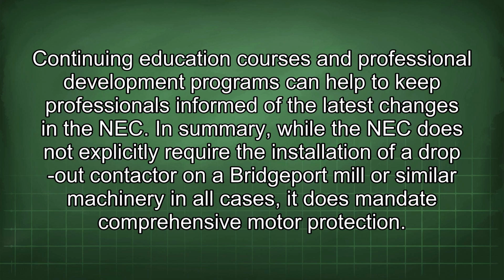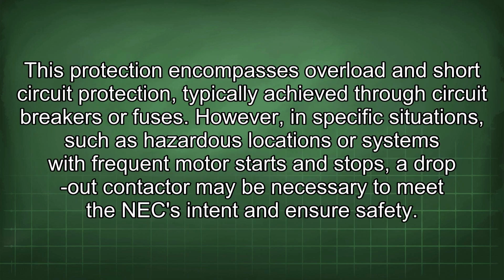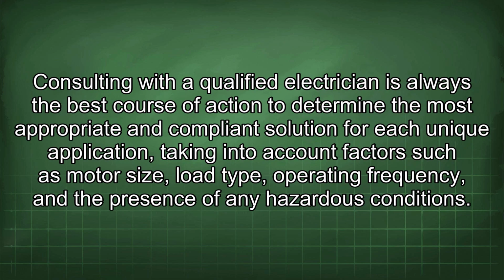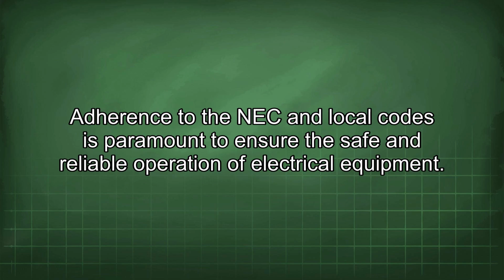In summary, while the NEC does not explicitly require the installation of a dropout contactor on a Bridgeport mill or similar machinery in all cases, it does mandate comprehensive motor protection. This protection encompasses overload and short-circuit protection, typically achieved through circuit breakers or fuses. However, in specific situations, such as hazardous locations or systems with frequent motor starts and stops, a dropout contactor may be necessary to meet the NEC intent and ensure safety. Consulting with a qualified electrician is always the best course of action to determine the most appropriate and compliant solution for each unique application, taking into account factors such as motor size, load type, operating frequency, and the presence of any hazardous conditions. Adherence to the NEC and local codes is paramount to ensure the safe and reliable operation of electrical equipment.